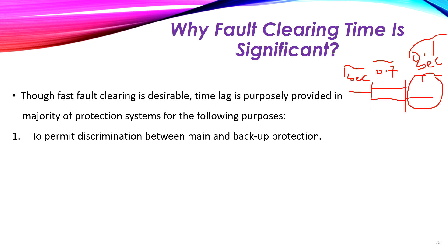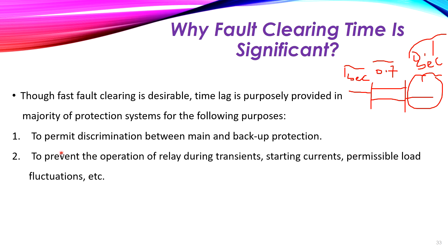Another reason why we cannot use a very small time: since fast relay and circuit breaker times are only a few cycles, why do we provide 0.1 seconds? Because we also need to prevent the operation of the relay during transients, starting currents, and permissible load fluctuations.